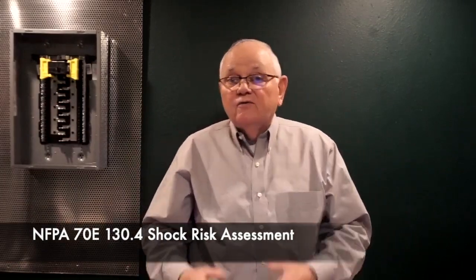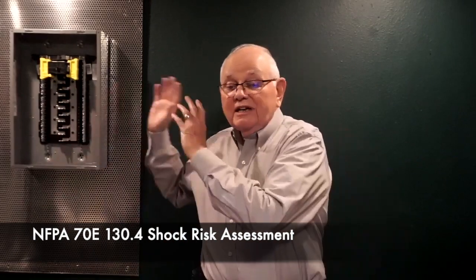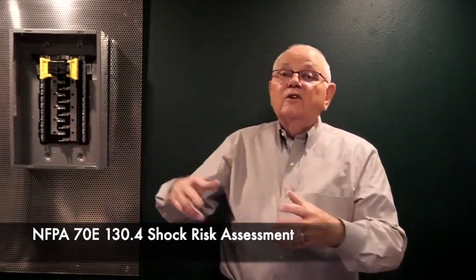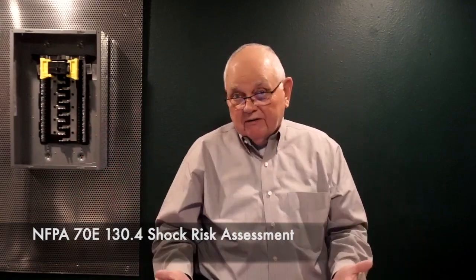Section 130.4 says that before we go out and do any job out in the field, we have to do a shock risk assessment. And that shock risk assessment tells us 3 things. We have to come up with 3 things in our shock risk assessment. Number 1, we have to identify the voltage hazards. What is the shock hazard? Well, it might be a 240 volt panel board, a 480 volt controller, or a 4160 volt circuit breaker that we're going out to operate or something like that. So we have to identify whatever those voltage levels are and the potential hazards there.